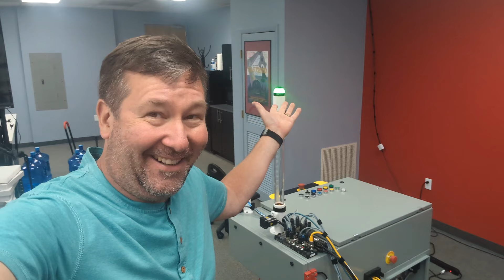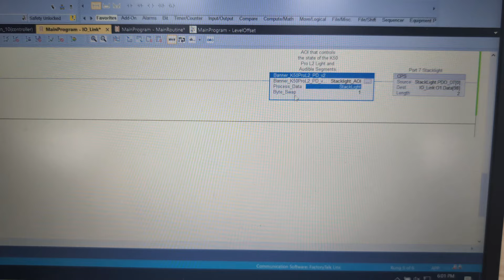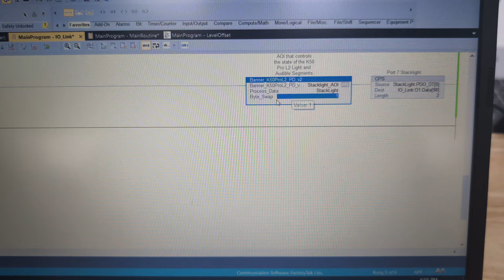Okay, so very exciting to get a light on, but it's more than just a light on, all the I/O link is tested. I ran into one hitch though. Compared to the old I/O link, all the bytes were swapped on this, which usually isn't a big deal. In fact, if we look at this stack light add-on instruction right here, there's a swap byte, and you just stick a 1 in that and it fixes it.